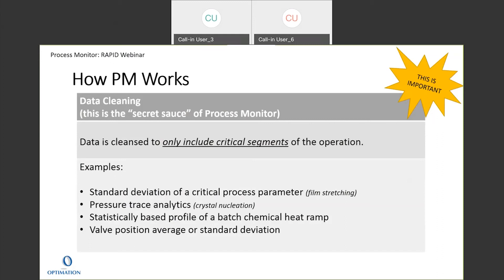Once the nucleation happened, you went through a growth mode where you basically grew these crystals, wanting to have a very uniform size across all the different dimensions of the crystal. So what we did was measure at up to a thousand hertz — measuring the pressure, flow, and temperature profiles at this nucleation time. Then we'd do statistics on it to ultimately show what was varying. We'd make sure that the valves, the temperature elements, and all the different elements were operating exactly the same every time you ran a batch, to make sure that you ended up having a consistent product.